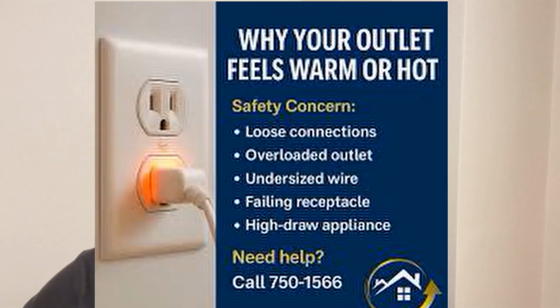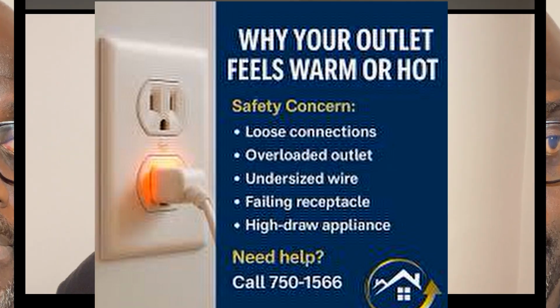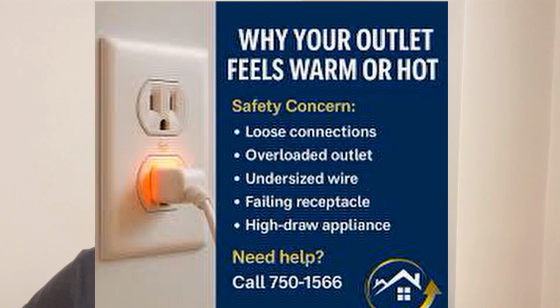Every loose connection creates a resistance. Resistance creates heat. Heat creates arcing. Arcing ignites surrounding materials. And that's how the fire starts, okay? It does happen, as we know. And most of the time, it's due to not tightening the screw properly enough. Now, these disasters can happen, unfortunately. It's an unfortunate thing. And they can happen frequently for a number of reasons I mentioned already. Also, you can have some screws that are not tightened properly, mixed copper and aluminium conductors, cheap terminals not rated for the load.